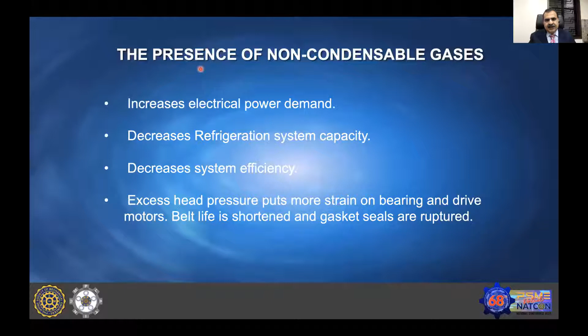Now, as the air in the system increases, it also increases the pressure and the temperature on the head side, or discharge side, of the compressor, which puts more strain on the bearings and drive motors. Belt life gets shortened and gasket seals are continuously ruptured. So the compressor maintenance cost goes high. Also, the increased pressure leads to increased temperature, which shortens the life of the compressor valves and promotes breakdown of the lubricating oil. As I told you, the lubricating oil is mostly made from hydrocarbons. Those hydrocarbons can again become non-condensable gases.